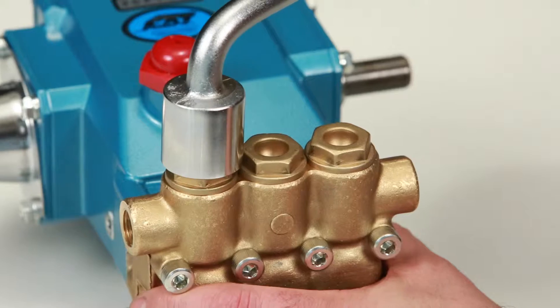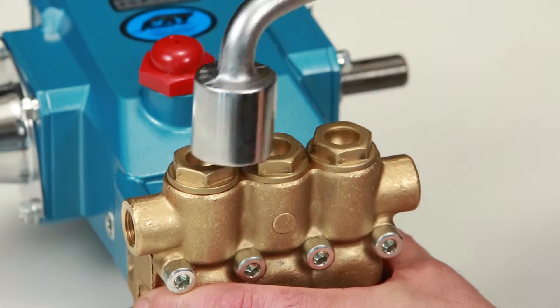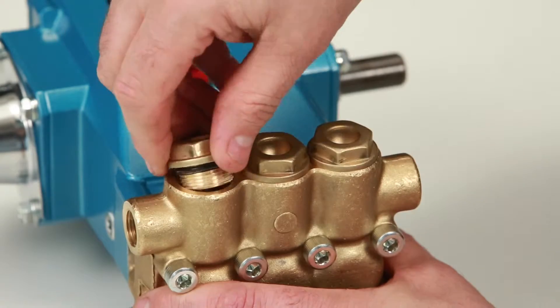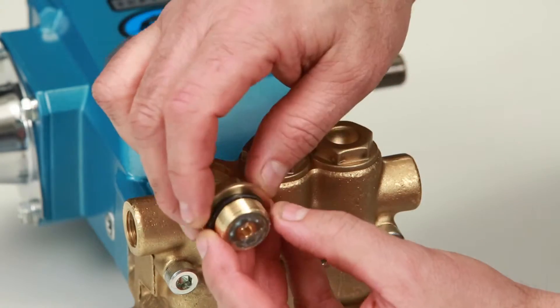To begin servicing the valves, remove the valve plugs using a 24mm hex wrench. After removing the valve plugs, inspect the O-rings for cuts, nicks, or any damage.